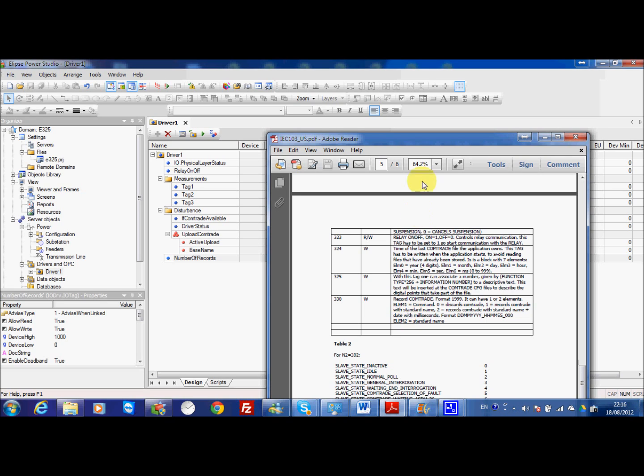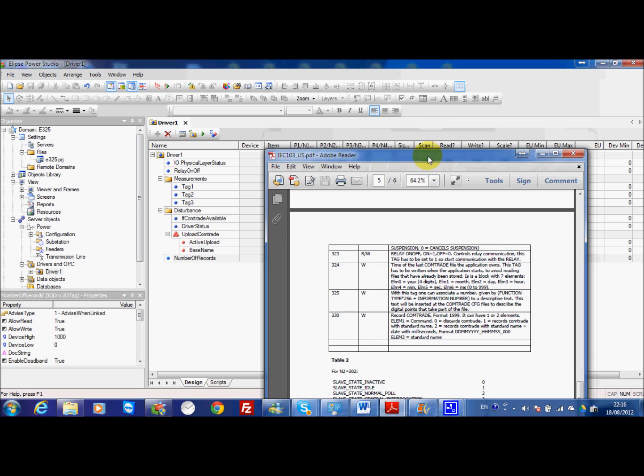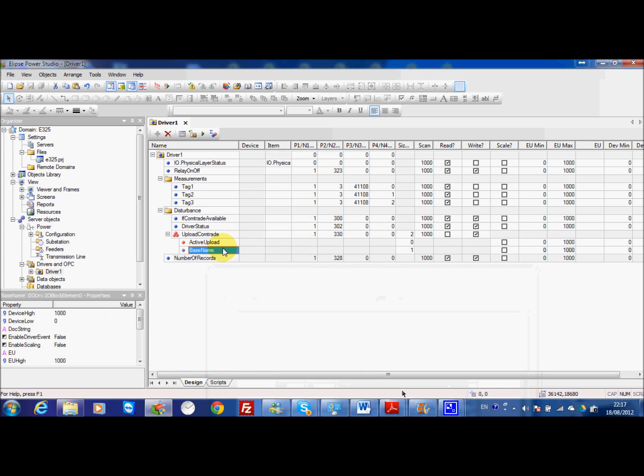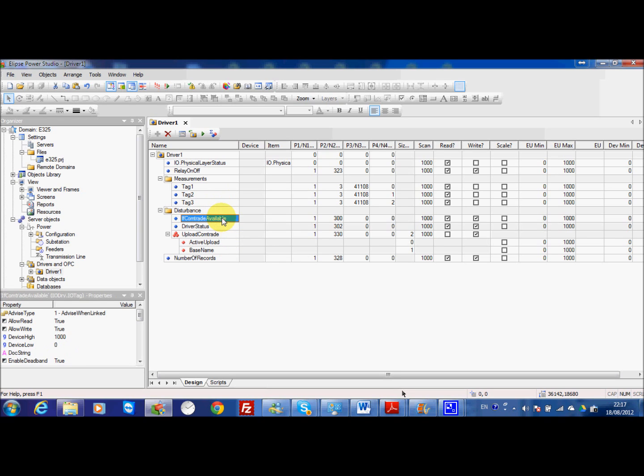Here this is to activate the comtrade uploading and also to give information about the base name, which means that if I want I can give a new name when the comtrade will be ready and stored in my computer. The system will give you the name I can specify here for this specific tag. This one, active upload, will be the tag I need to set to 2 when the driver status or the if comtrade available have the correct value.